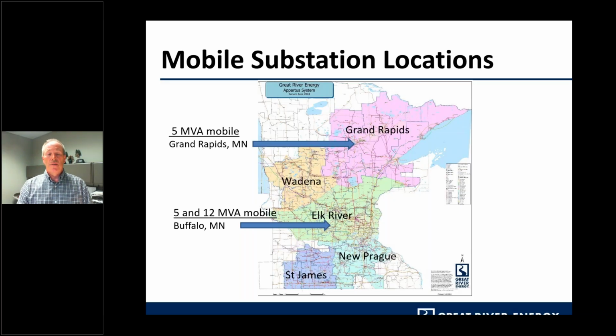Great River Energy has 2 locations for our mobile substations. In Grand Rapids, Minnesota, we have a 5 MVA mobile sub, and in Buffalo, Minnesota, we have both a 5 and a 12 MVA mobile substation. These mobile substations are stored inside buildings to prevent weather-related damage that can occur here in Minnesota. Our mobile substations are designed to model our cooperative members' distribution substations. They have a high side switch, multi-tap transformer, a low side recloser, protective relaying, metering, and a communication package installed, along with both a low side cable and regulator trailers, and some even have high side switch trailers too.